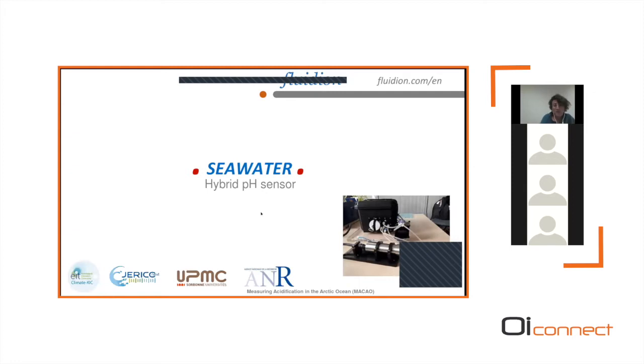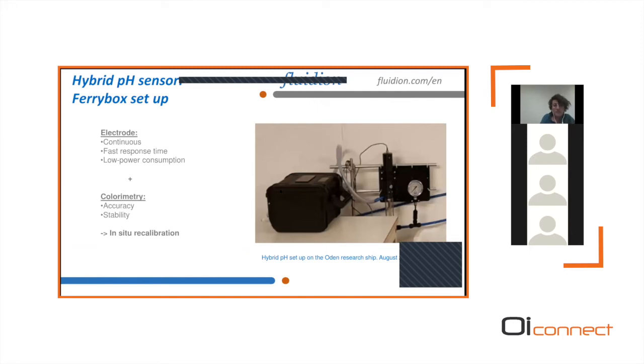Now for the seawater application, this is our hybrid pH sensor. So the idea here is to combine 2 different sensors that we have mentioned earlier, to take advantage of both. First, an electrode, in order to have a continuous and fast response time with low power consumption, combined with a colorimetric analyzer to have high accuracy and long stability in time, and to enable an in-situ recalibration of our electrode data. So here it's a setup, which was a ferry box setup plugged on the underway of the research ship. And you can recognize here our colorimetric analyzer, which has been adapted for seawater measurement.